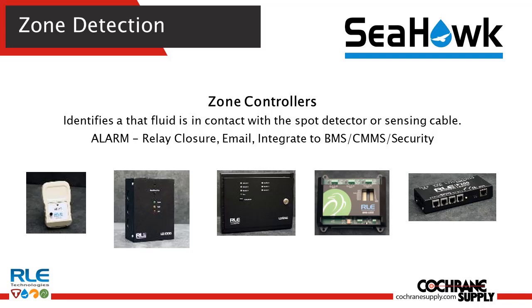So the LD310 on the left can handle up to 300 feet of sensing cable, has an audible, visual, as well as a relay closure. The LD1000 next to it can handle up to 1,000 feet of sensing cable. Again, the audible, visual, as well as the relay closure, but then also can integrate via Modbus RTU. The guy in the middle is an LD-RA6, which is a 6-zone leak detection, so each zone would have their independent alarm notification, and can also talk Modbus RTU. The guy second to the right there is part of our Raptor line, which is a 3-zone leak detection. Communication can be MSTP BACnet or Modbus RTU, selectable on the controller, identifying 3 zones of leak detection, integrating into a building automation platform.